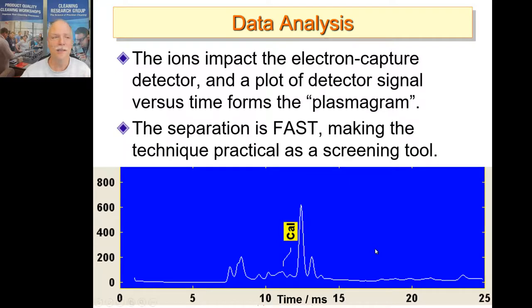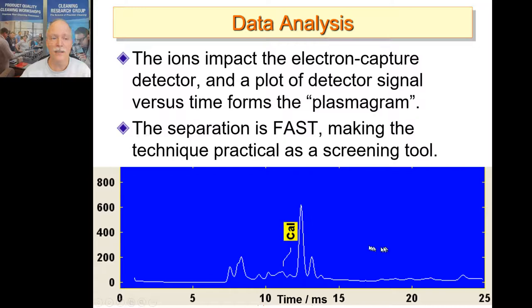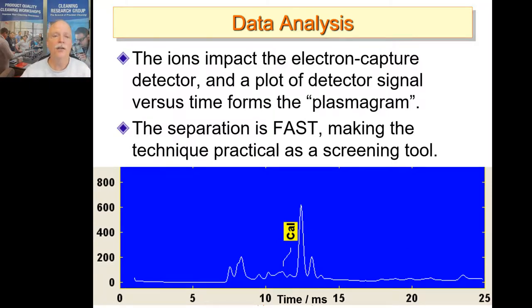The ions impact an electron capture detector, and a plot of the detector signal is called the plasmagram — the separation is very fast. This is an example of a plasmagram showing the calibration signal: when nothing is in the inlet, you pull the signal from the methylene chloride calibration gas that's always present. This serves as a validation of the technique — if you can see the calibration gas, you can confirm the detector is working, the counterflow is working, the ionization is working, and the ionization gas is present. You can also insert standards to check performance against known explosives.